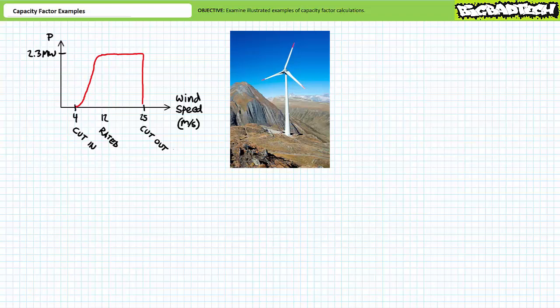A wind turbine power curve is typically defined by three points: the cut-in speed, the rated speed, and the cut-out speed. The cut-in speed, typically around 4 meters per second, is when the turbine actually starts producing power. Between the cut-in speed and the rated speed, power increases. At the rated speed, typically around 12 meters per second, the turbine generates its nominal or nameplate value — in this case 2.3 megawatts. Between the rated speed and the cut-out speed, power output flat-lines at the nominal value. At the cut-out speed, typically around 25 meters per second, the turbine shuts down to prevent damage.